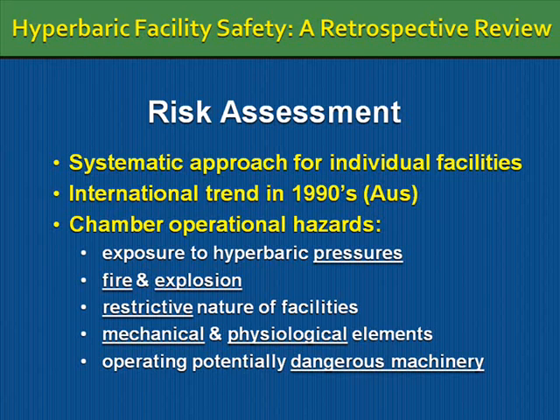If you think about a hyperbaric chamber as a physician, the patient goes into the chamber, the door is closed, the chamber is then pressurized, and now you lose your ability to all of a sudden change your mind. You can't simply open the door and take the patient out. So if the patient goes into some form of distress, you're stuck with the patient under pressure, and you have, in the best case, between 4 and 6 minutes in a multi-place chamber to get the patient out again before you can apply whatever you need to do to the patient. But if something goes wrong, you cannot simply unwind the clock and get access to the patient.